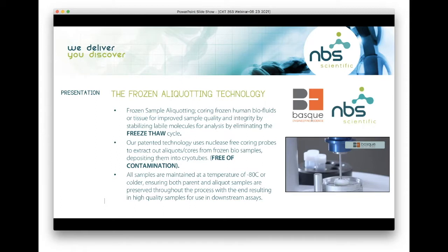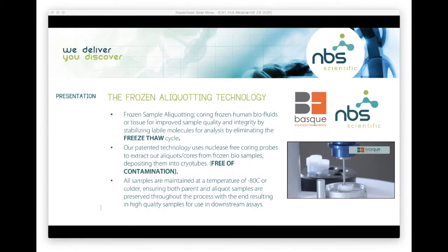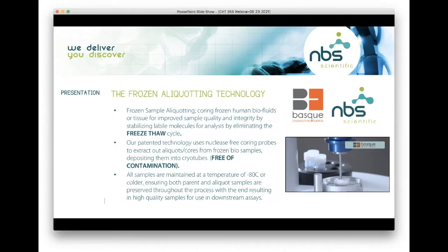So what is frozen aliquoting technology? Frozen sample aliquoting is coring frozen human biofluid or tissue for improved sample quality and integrity, by stabilizing the labile molecules for analysis and by eliminating the freeze-thaw cycle. Our patented technology uses nuclease free coring probes to extract aliquot cores from the frozen bio sample, depositing them into cryo tubes free of contamination. All samples are maintained at minus 80°C or colder, ensuring both the parent and aliquot samples are preserved throughout the entire process, with the end result being a high quality sample for use in a downstream assay.